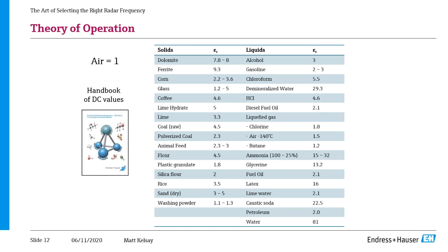A little bit different on this radar side is that it reflects based off of the dielectric constant of the material. So you might see different terms or signal symbols for this. So in this chart, you see epsilon, you might see DC value, DK value, dielectric, lots of different things you might see. They're all pretty much the same. So when we look at this, air is kind of a baseline dielectric. It has a dielectric of 1. Water is one of the highest dielectric values at around 80.